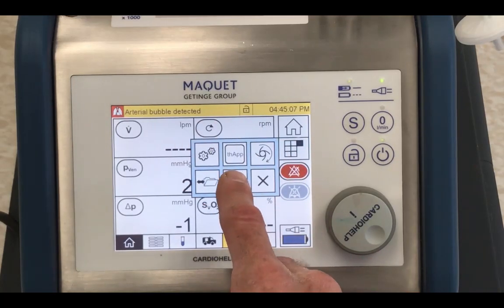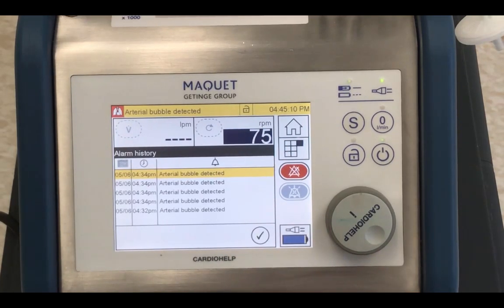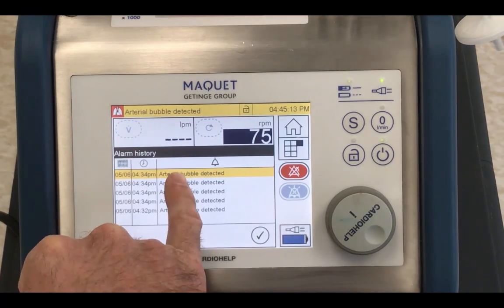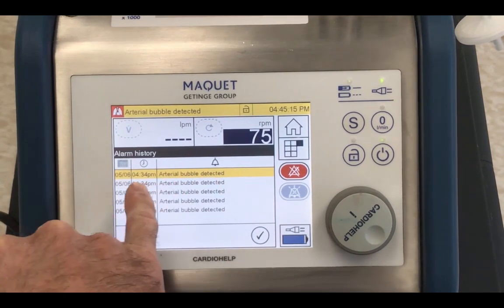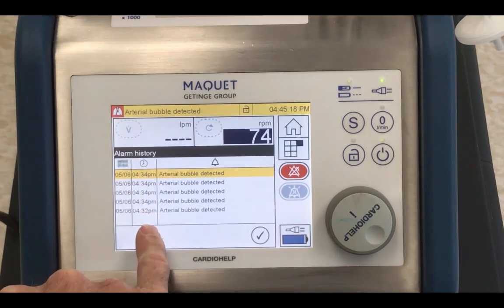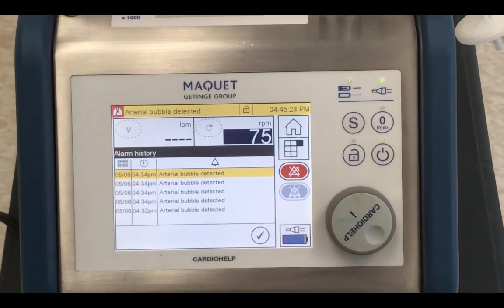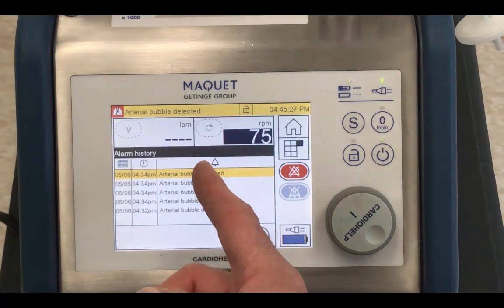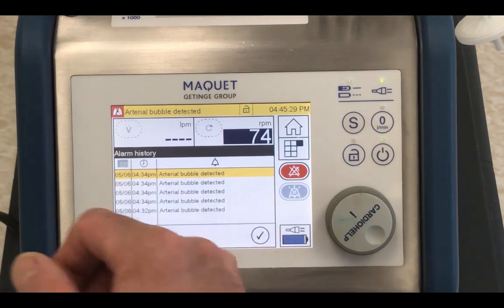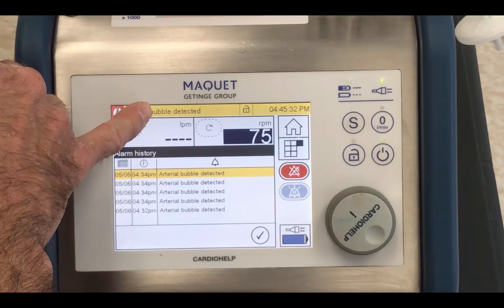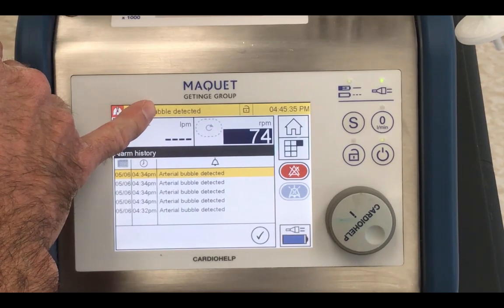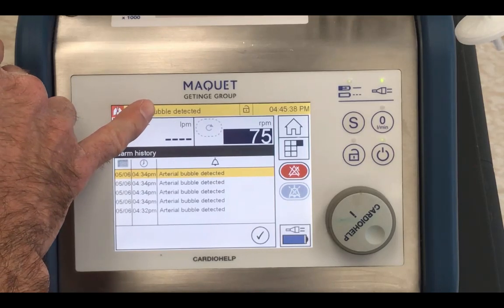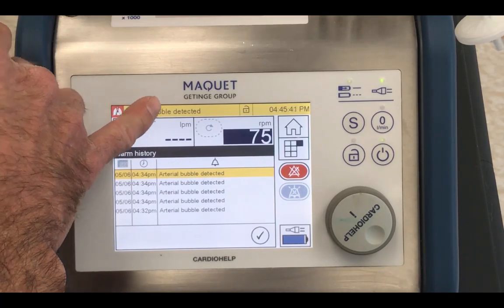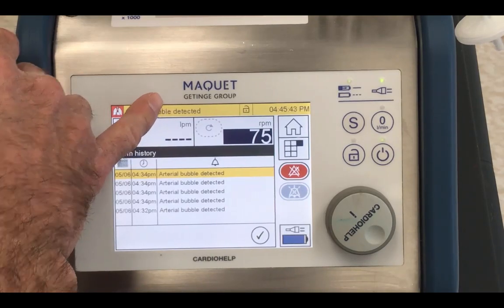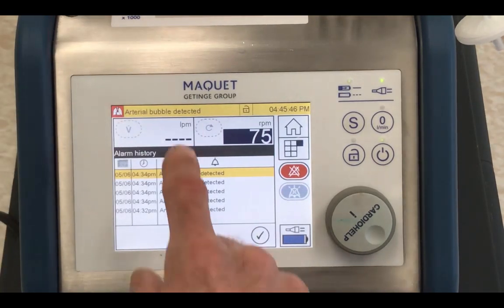Look at the next menu in line, and this is going to be the list of running errors. We can see that we've had a bubble detector, arterial bubble detected on this date at that time, and all these other times as well. So this is the alarm history. It's not infinite. It doesn't go all the way back in time. There's a certain number that it records, and it tells you this is now the order in which they happened, whereas the display up here is telling you the current most important error. This might have happened a while ago, and 2 things have happened since then, but since it's a yellow-coded error, it's still on top, and the white-coded errors are not being displayed because you can only display one thing at a time.